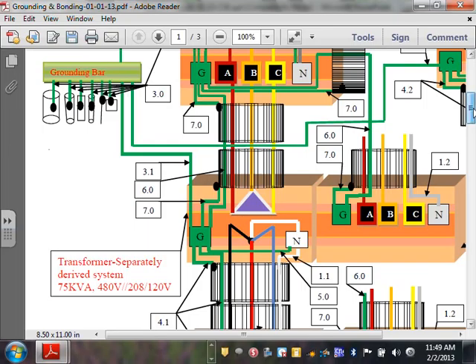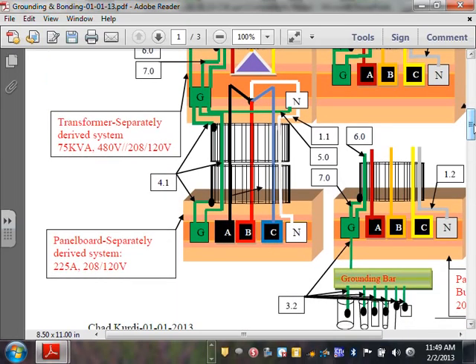Okay, so we got this transformer, my friends, and then that's about it. So I went into my panel with 4 conductors here in this case. I have my neutral, 3-phase, and my supply side bonding jumper, and I bonded flex from both sides. I do not bond again. You can't bond again. Any comments, guys?